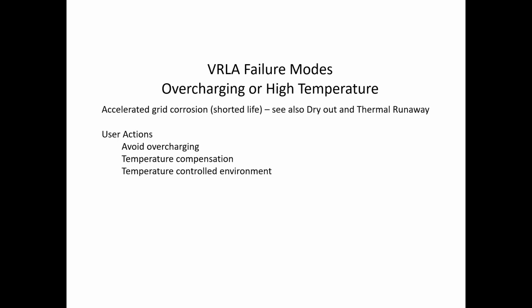Overcharging or high temperature. The grid corrosion, I had mentioned before, is kind of the process of a battery just as it's in service. We do try not to overcharge. This is why we say equalization can be dangerous, with people just forgetting that it's in equalization. Again, once you accelerate grid corrosion, there's no return, there's no fix for that other than replacement of the battery. So that's permanent damage.